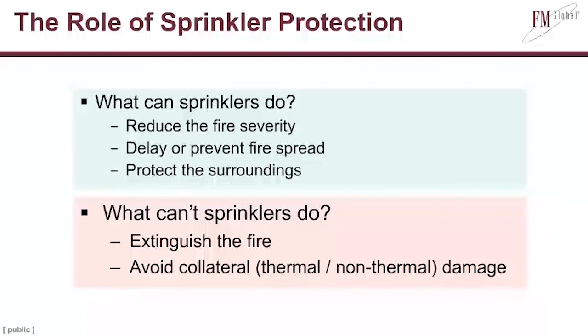What can't they do? They can't extinguish the fire. You're not putting water directly onto the burning combustibles. You're putting water onto the metal shell around the combustibles. So you don't have a very good transport to get your water to cool those modules. The other thing sprinklers can't do is avoid collateral damage. Certainly there's going to be thermal damage from the fire. There's also going to be non-thermal damage such as smoke and water damage as well. So there are other protection systems that can target differently, but sprinklers are going to have that collateral damage associated with it.